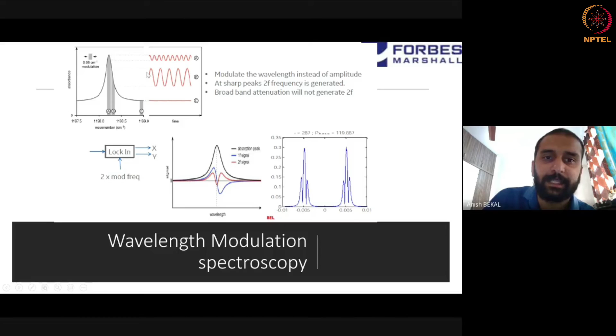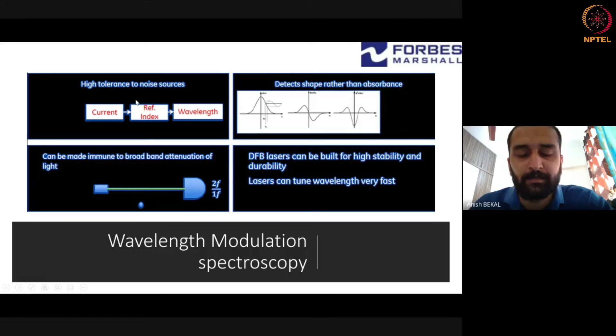That means this particular system is sensitive to the shape of the curve. It is not really sensitive to the absorbance per se, but to the shape of the curve. So if you have two absorption spectra sitting next to each other, of two different gases, you can separate them very nicely. And there are several other advantages, because you're using a lock-in, so you can get a very high sensitivity and things like that.